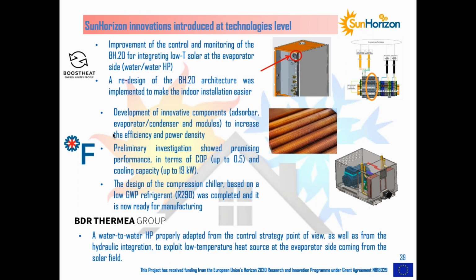Regarding the hybrid Fahrenheit machine development, as mentioned before, it's mainly on the component side, especially optimization of the main components: the adsorber, evaporator and condenser of the adsorption machine, and also the integration of the vapor compression machine within SunHorizon. Fahrenheit decided to go for a low GWP natural refrigerant, R290, which will be manufactured and installed in parallel to the adsorption machine for the application at the San Cugat demo site.